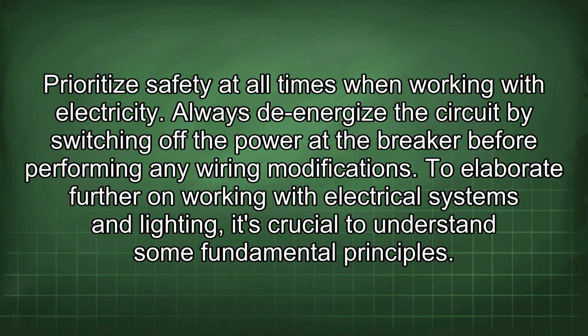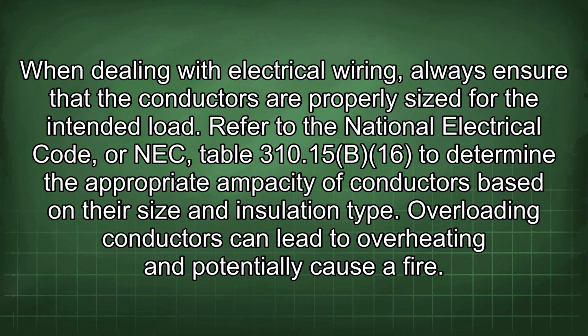To elaborate further on working with electrical systems and lighting, it's crucial to understand some fundamental principles. When dealing with electrical wiring, always ensure that the conductors are properly sized for the intended load. Refer to the National Electrical Code, or NEC, Table 310.15(B)(16) to determine the appropriate ampacity of conductors based on their size and insulation type. Overloading conductors can lead to overheating and potentially cause a fire.